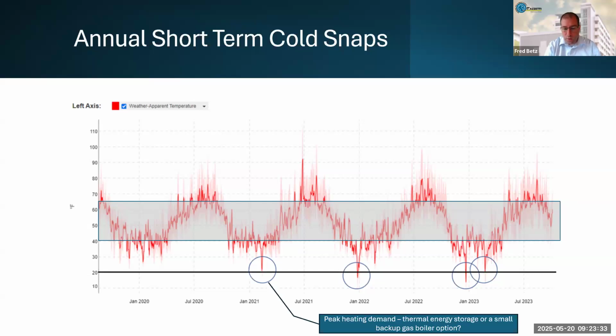Is it does get cold, albeit not often, right? So the dark black line there is the 20 degrees Fahrenheit. That's what ASHRAE says is the 99.6 design conditions for heating. In reality, it gets colder than that. It gets down to about 9 degrees. And we've measured a few times there. And so, we have to cover those conditions.